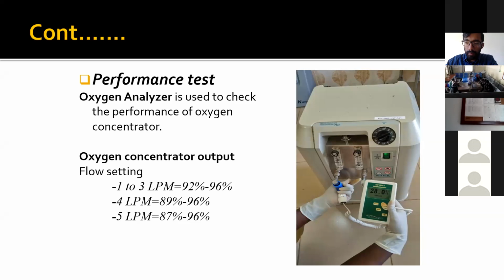So the oxygen analyzer is used to check the performance of the oxygen concentrator, and it checks the output against the flow setting, as you can see. From 1 to 3, it has to be 92 to 96%. At 4, it has to be 89 to 96% oxygen. At 5, it has to be 87 to 96.